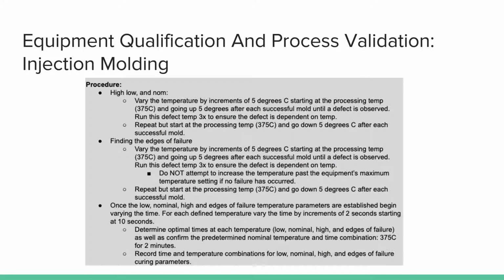So then an equipment validation was done for the injection molding machine to make sure it is installed properly and operates as intended. One part of the equipment validation is to determine the high, low, normal parameters and edges of failure. For the injection molding machine, the parameters were established by changing the temperature of the machine and the timing to create the mold for the catheter.